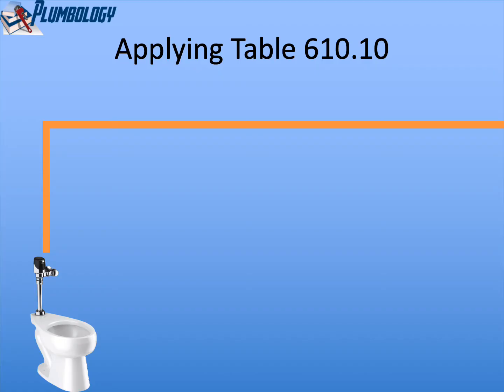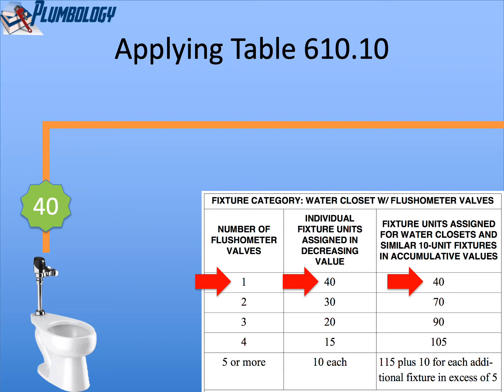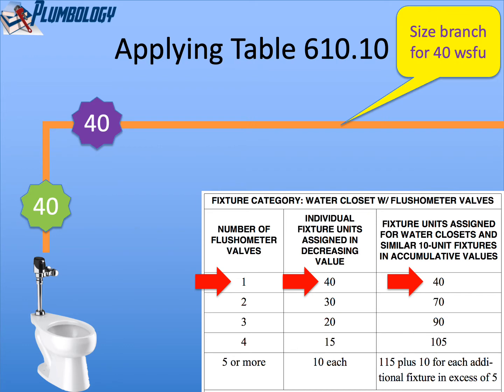Applying table 610.10. We'll start simple with one water closet flushometer valve and only one pipe serving that valve. According to the table, if we have one water closet flushometer valve, that valve needs to be given a value of 40 fixture units. So we write 40 near the flush valve. The water piping serving that flush valve has an accumulative value of 40 fixture units, so the piping would also have 40 fixture units on it. If we were sizing that pipe, we would size that branch for 40 water supply fixture units.